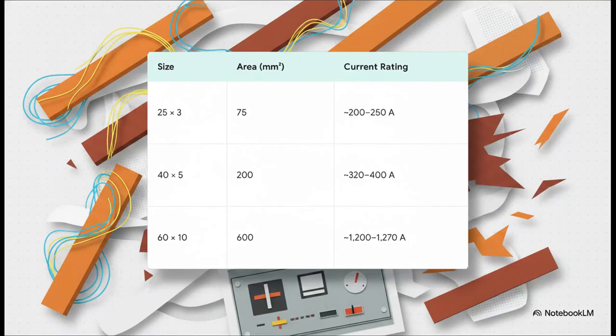Now, when you're sizing copper bus bars, you might think it's just a simple formula based purely on the cross-sectional area, right? Like a 25 by 3 millimeter bar handles about 200 to 250 amps, while a beefy 60 by 10 bar handles roughly 1,200 to 1,270 amps. And sure, rated continuous current is definitely the starting point, but here's a truly fascinating fact. Pure area-based rules completely lose their usefulness at larger sections because of the skin effect and proximity effect. High frequencies and larger conductor sizes actually change how the current flows. That means things like enclosure heating, ventilation, and fault duty heavily dictate the final size.